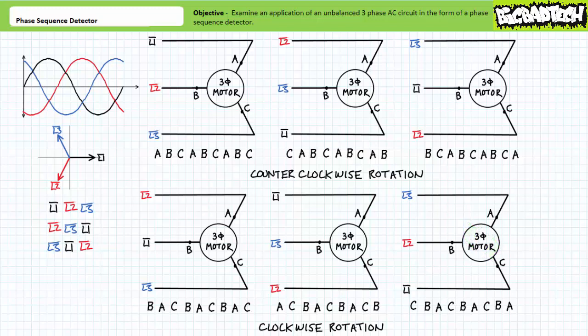The larger point is that phase sequence established by a three-phase AC source between L1, L2, and L3 is fixed and unalterable. However, they can be applied at the point of use in any manner deemed suitable for the application. Wired in one fashion, a motor would drive a conveyor belt forward and send an elevator up. Wired in another fashion, a motor would drive the same conveyor backward and send the elevator down. A user should have some idea of the phase sequence prior to wiring up a motor, as primary wires might lack proper labels or identifying colors above a certain gauge, leaving a user with three otherwise indistinguishable black wires and the same line-to-line differential between them.